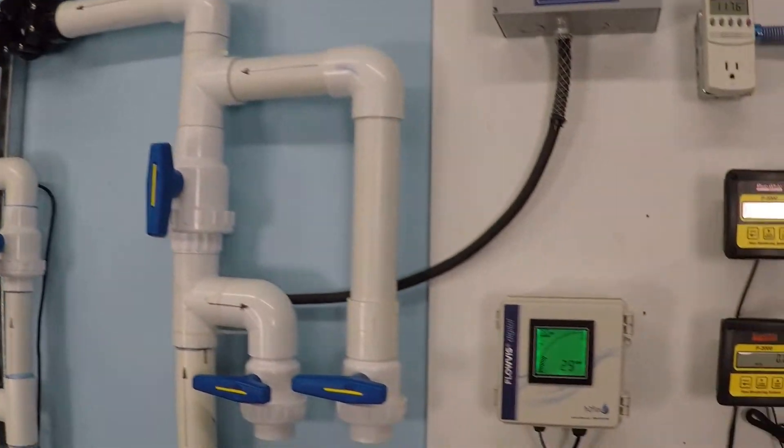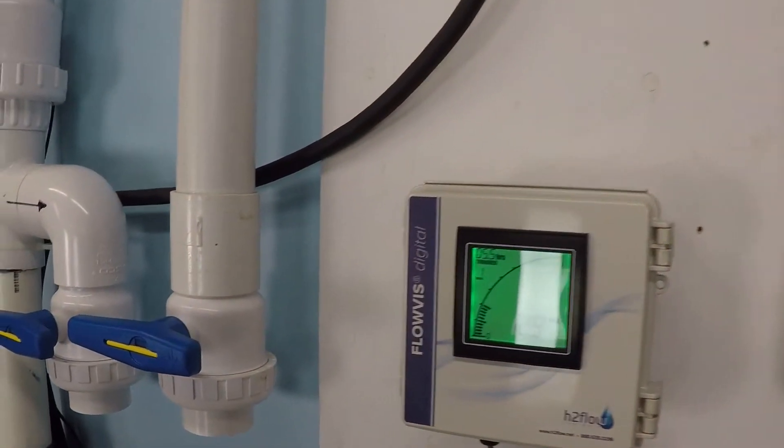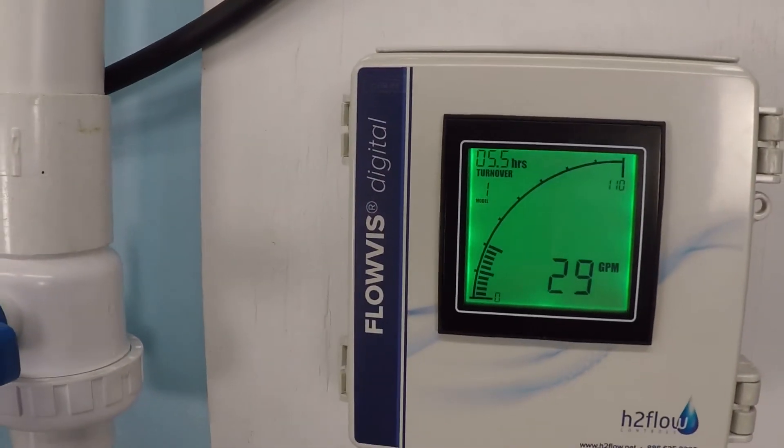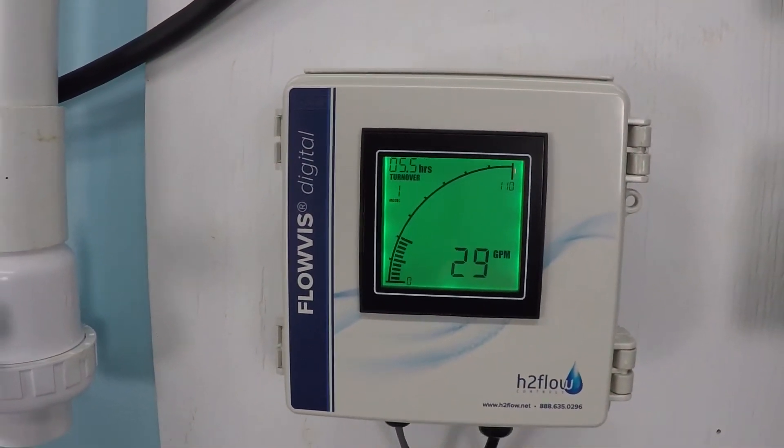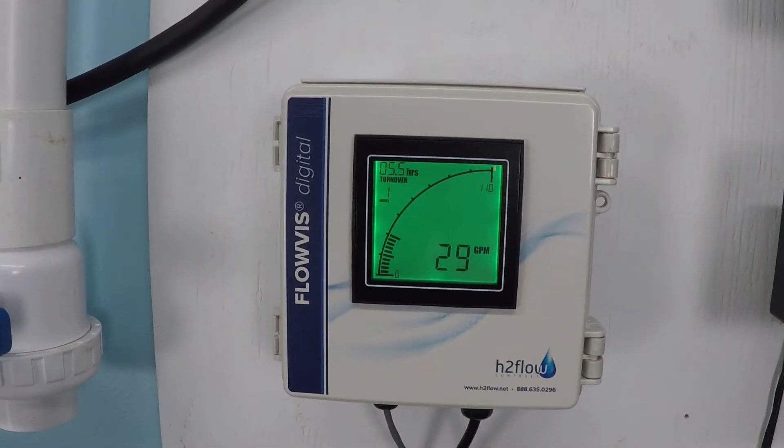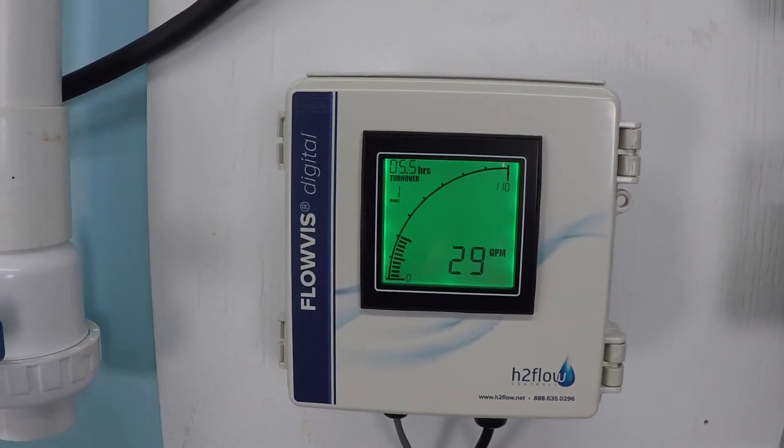So what I can see from 1000 RPM of operation is that we're achieving just under 30 gallons per minute of flow, which is actually quite a bit of flow and that's the point of this video. I want to show you how much a little bit of flow can add up to be.